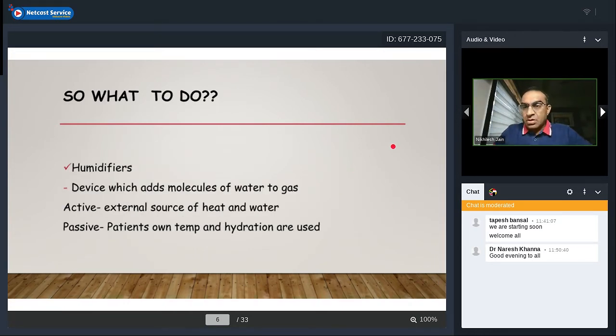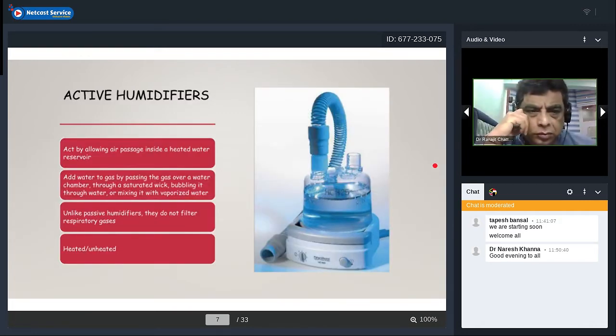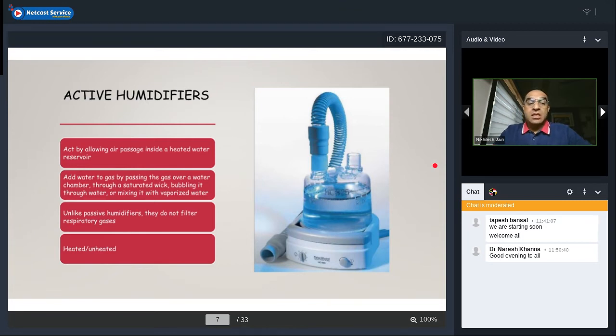To tackle this situation, humidifiers must be added. Humidifiers are devices which add molecules of water to a gas. Active humidifiers use an external source of heat and water; passive humidifiers use the patient's own temperature and hydration. Active humidifiers work by allowing air passage inside a heated water reservoir — passing gas over a water chamber, bubbling it into water, or mixing it with vaporized water. They are not meant to filter respiratory gases, unlike passive humidifiers, and can be either heated or unheated.